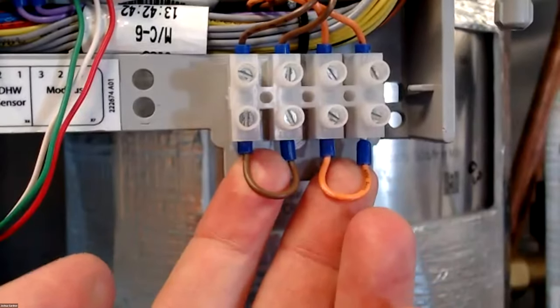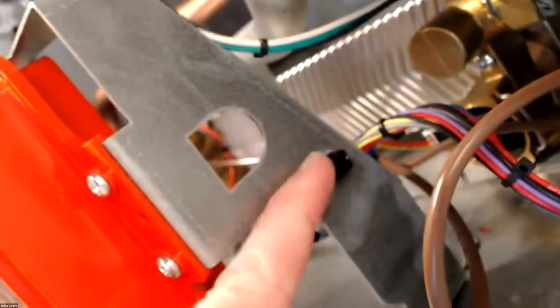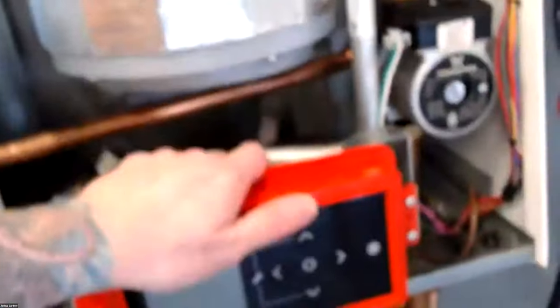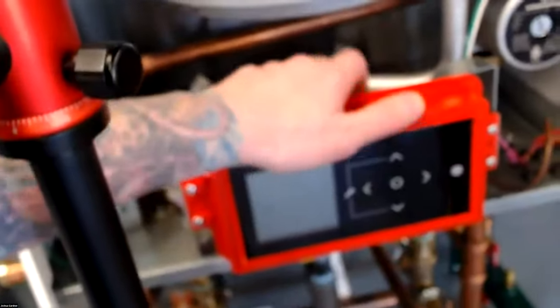And then going to the low water cutoff that you guys want to tie in, auxiliary, the probe type, we have connections right here where those will wire into. I think it's on the Watchdogs. There's a brand of low water cutoff that has a Molex plug and it matches up to this on this side. Guys have plugged it in there. Doesn't go there. Control will go dead. It won't kill it, won't break it, but the screen will go off and then we'll get a call that there's no heat and we can't get control on because they installed their low water cutoff up here and they plugged it in here and it rendered the control useless. So just note the low water cutoffs wire into these two connections.